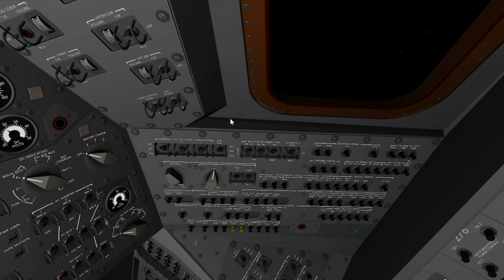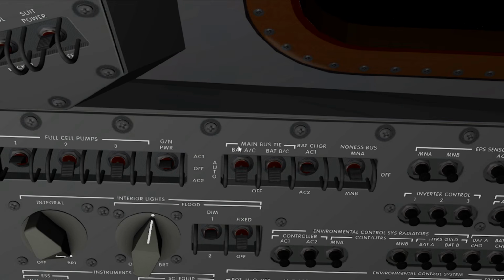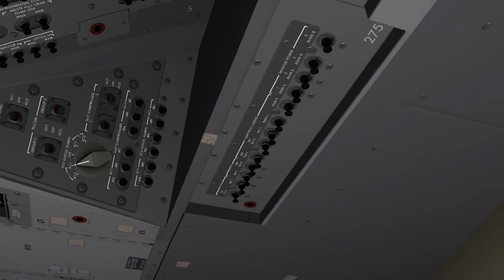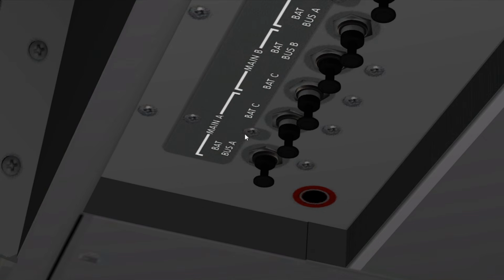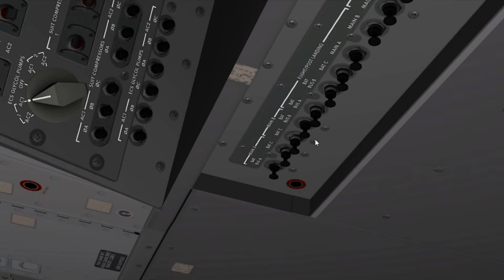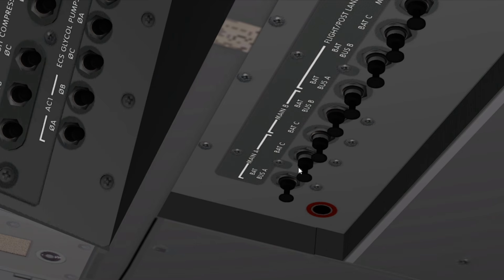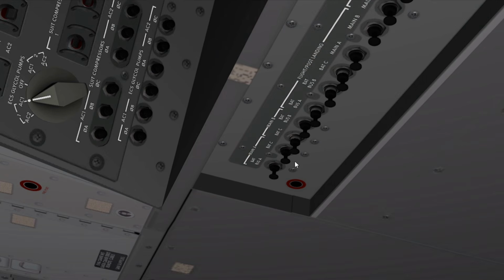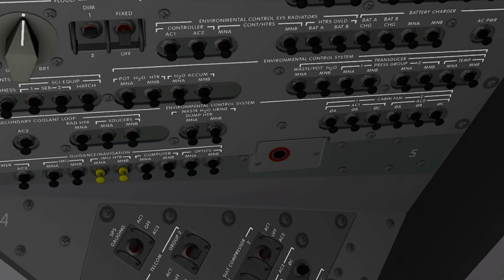The other thing that came up is the main bus ties. I would like to point out that when you flip, for example, bat AC tie to on, only battery A is getting tied right now, and the reason is because the battery C circuit breaker here on panel 275 with main bus A is open. We close that, we power up battery C.